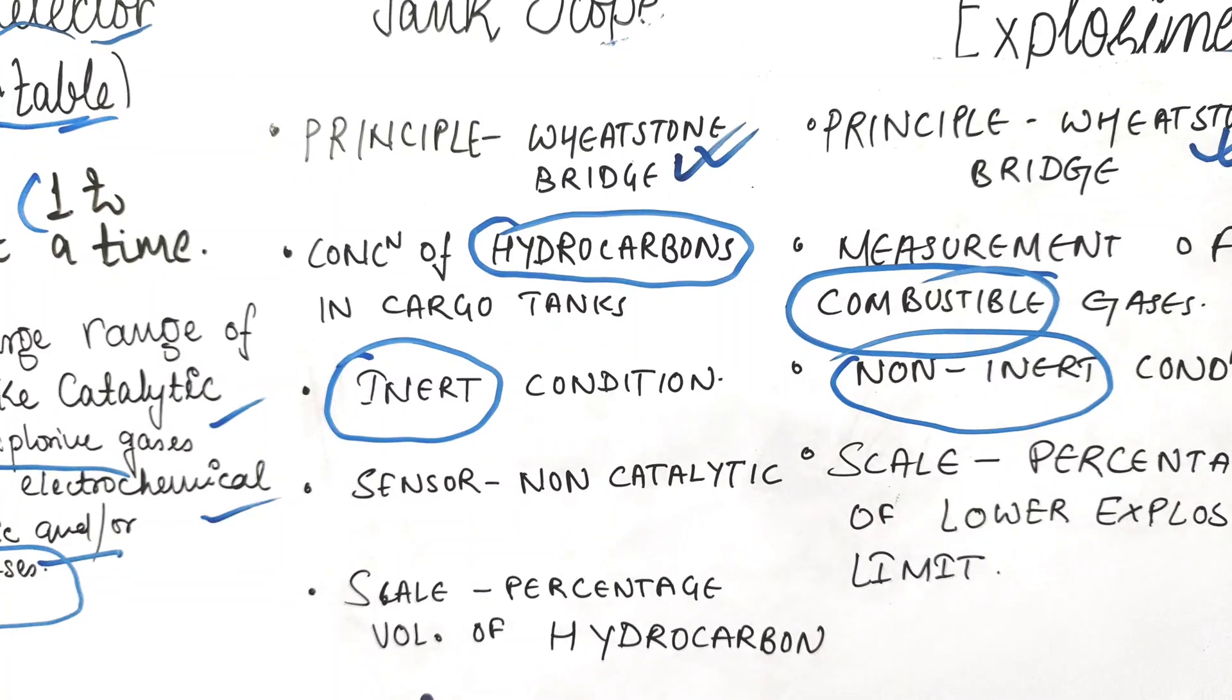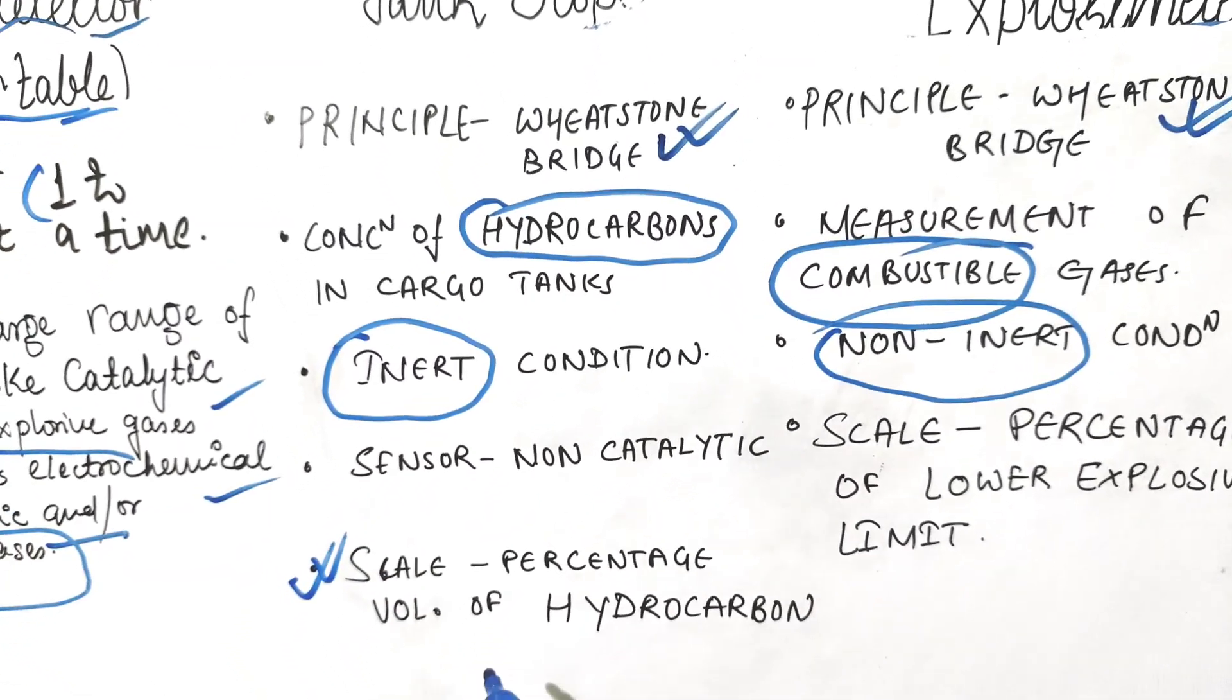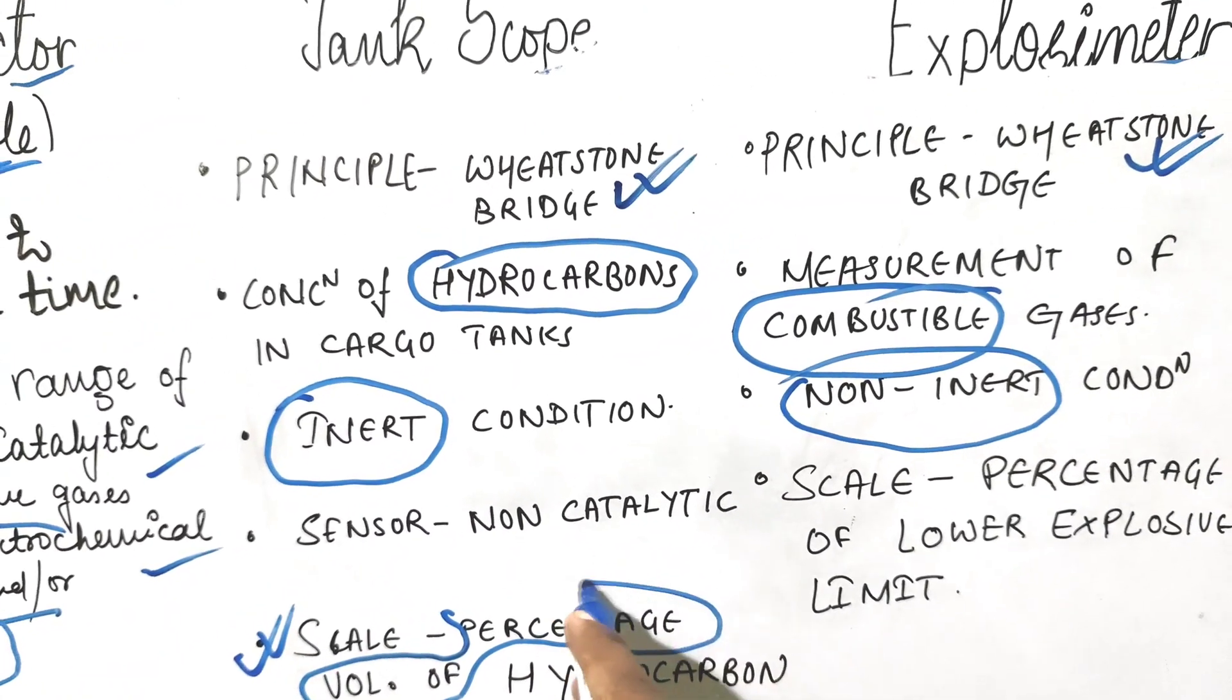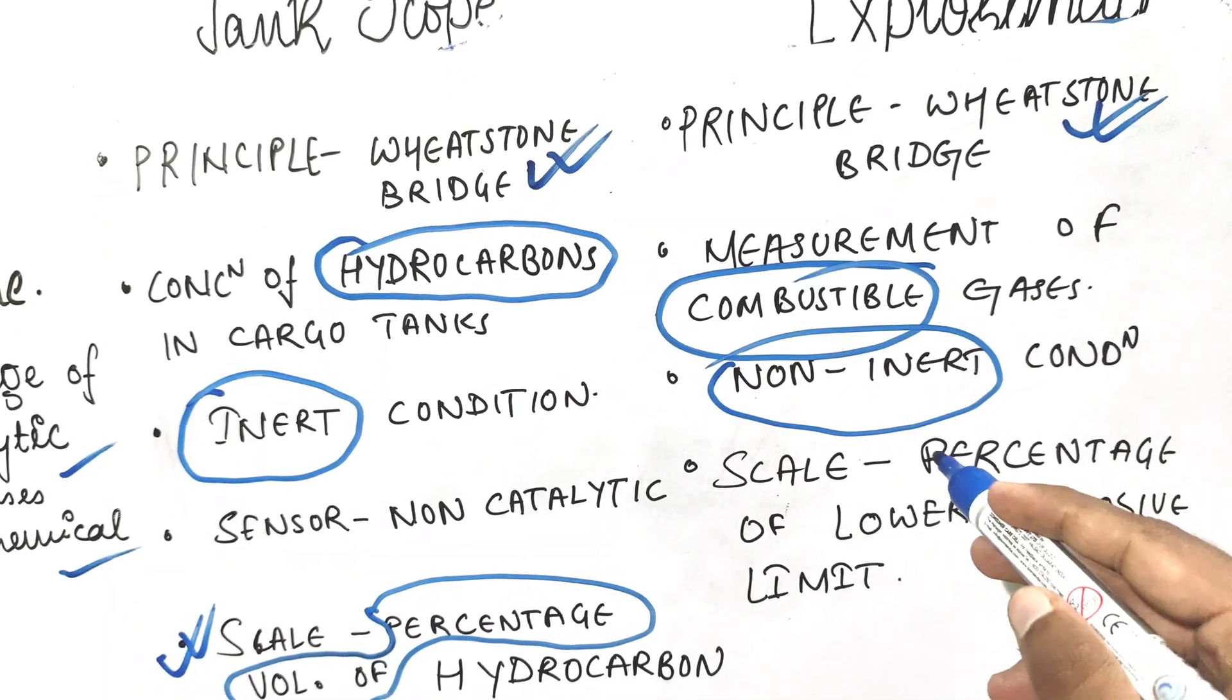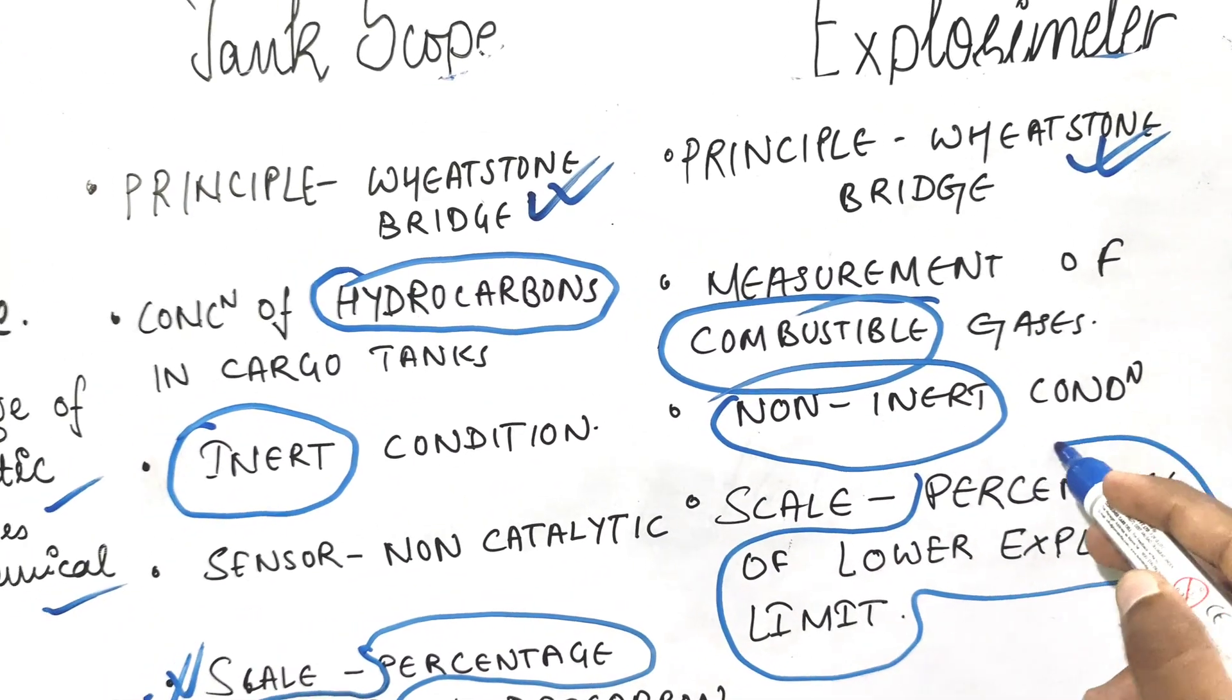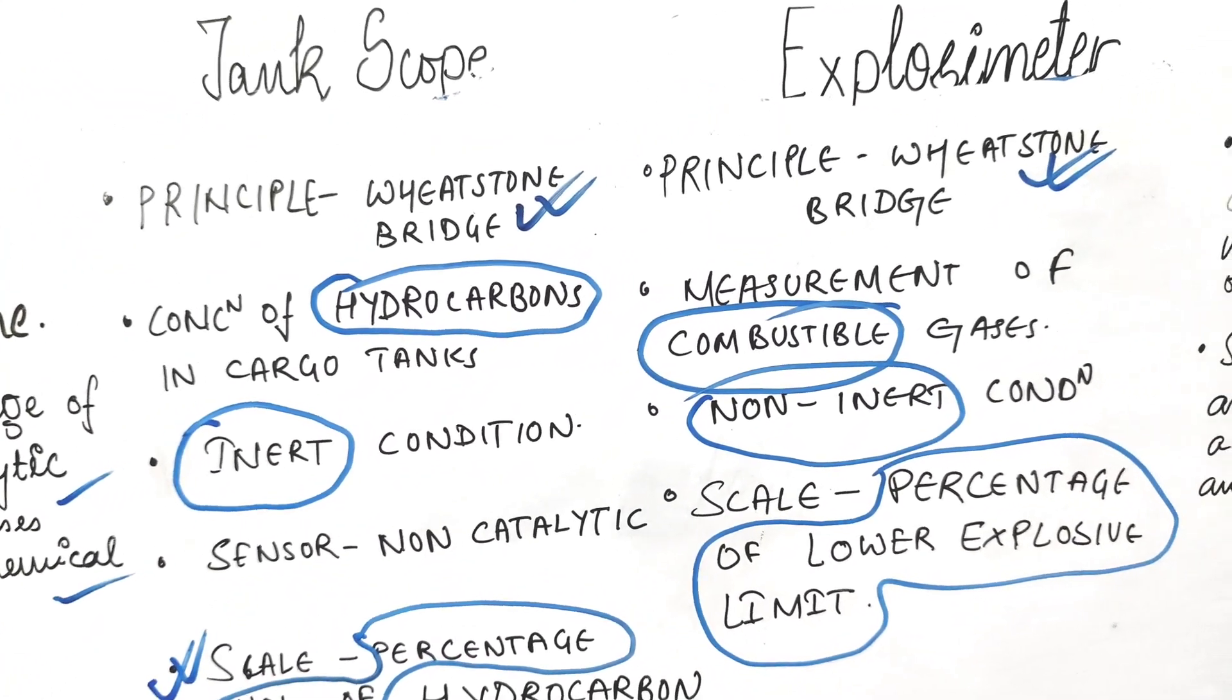There is also a difference in the scale. For tankoscope, we have percentage volume of hydrocarbon, whereas in case of explosimeter we have percentage of LEL—Lower Explosive Limit. This is very important and you need to know it.